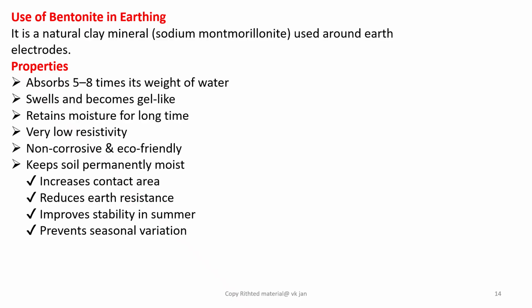Friends, this slide shows the use of bentonite in earthing. It is a natural clay mineral used around earth electrodes. Properties: it absorbs 5 to 8 times more water. It swells and becomes gel-like. It retains moisture for a long time. It has very low resistivity. It is non-corrosive and eco-friendly. It keeps soil permanently moist, increases contact area, reduces earth resistance, improves stability in summer, prevents seasonal variation.